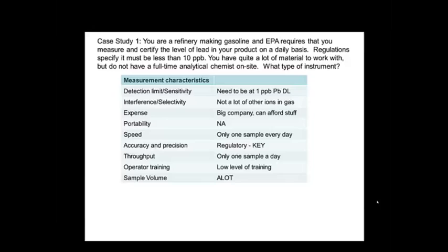For this I'm going to be reading, so I'll take my picture out. In this first case, you are at a refinery making gasoline, and there is a regulatory requirement specifying lead to less than 10 parts per billion. You have a lot of sample to work with, but you don't have a full analytical chemist on site. I like to set my detection limit about 10 times below the regulatory limit, so that's one part per billion. Big company probably has a good budget, but you don't need anything portable. The key measurement need is you must be able to measure one part per billion lead — tied to regulation — and do that precisely and accurately.